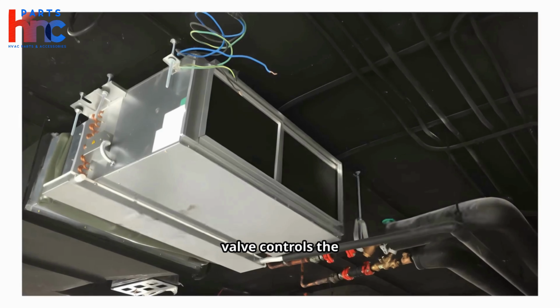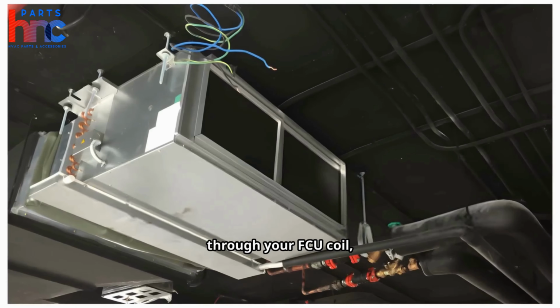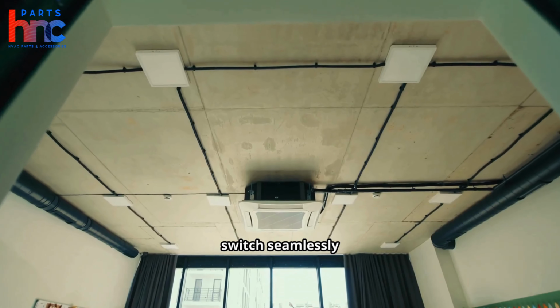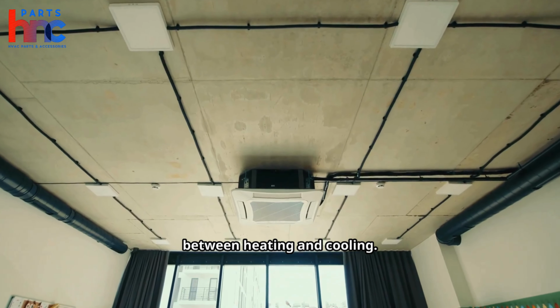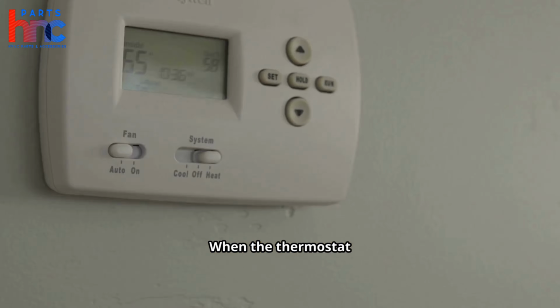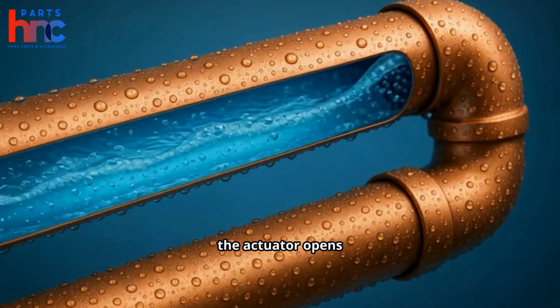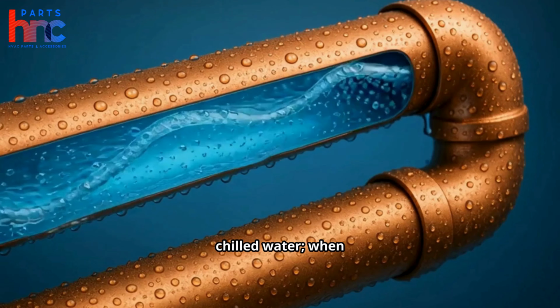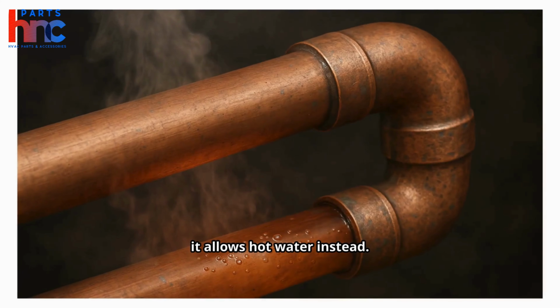The two-way zone valve controls the flow of hot or chilled water through your FCU coil, helping the system switch seamlessly between heating and cooling. It works in sync with the actuator. When the thermostat calls for cooling, the actuator opens the valve for chilled water. When heating is required, it allows hot water instead.